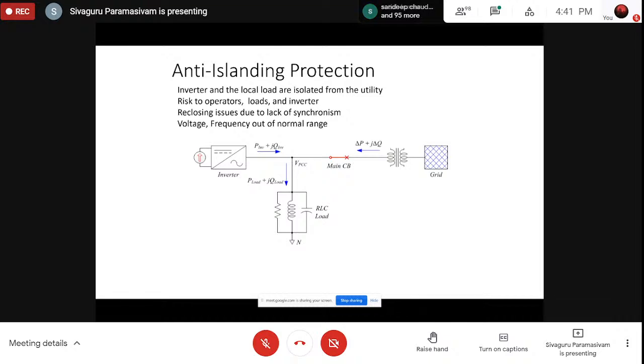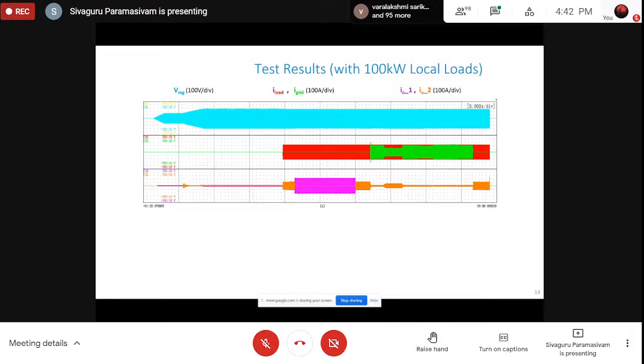So there are two systems, so please don't get confused here. One is the anti-islanding protection. Whenever we are working in a mainland grid, we should not pump the power back to the mains without any permission from the grid. And when the system is designed for island operation, like we have done projects in Andaman Island, there they say that, okay, if the grid is off, you can open the circuit breaker and you can form an island with your inverter. So it depends upon the authority's approval. We can do both the functions, and the control system is largely varying between these two applications.